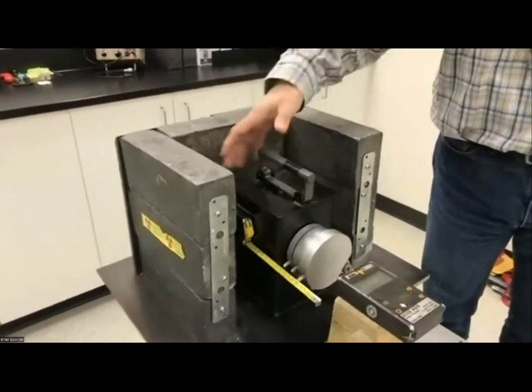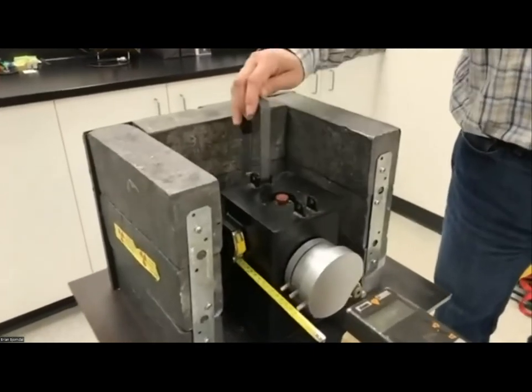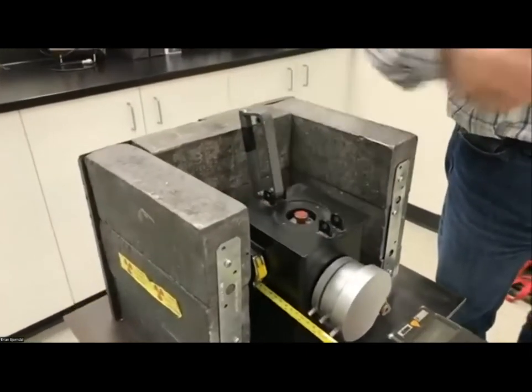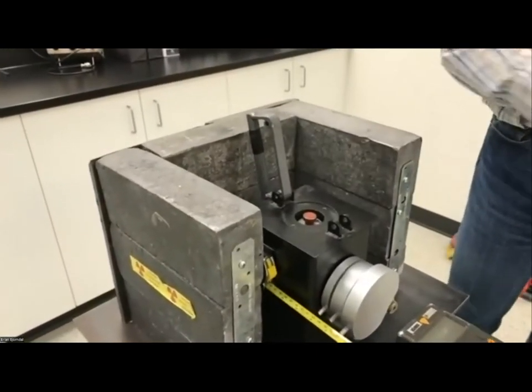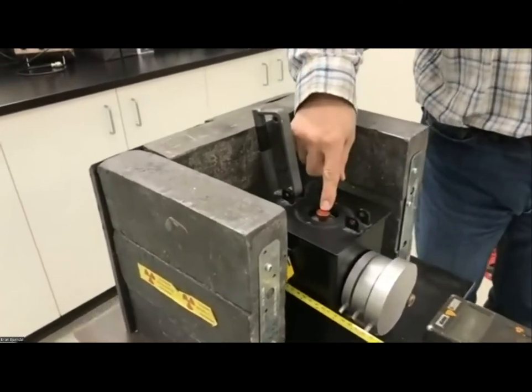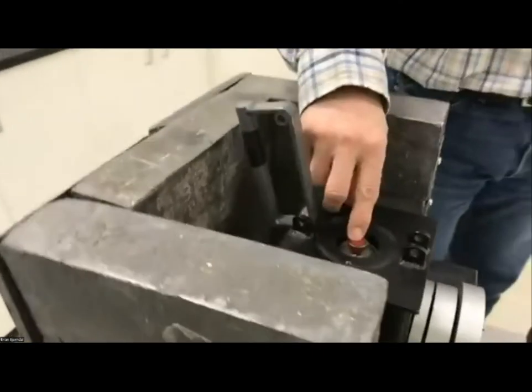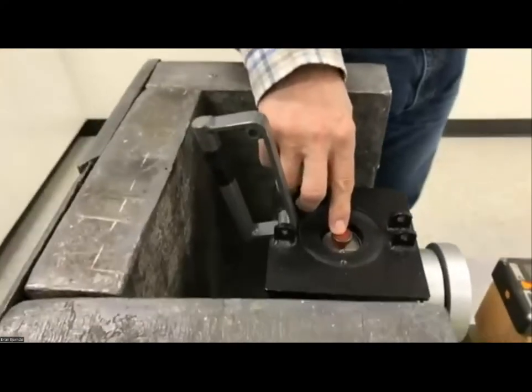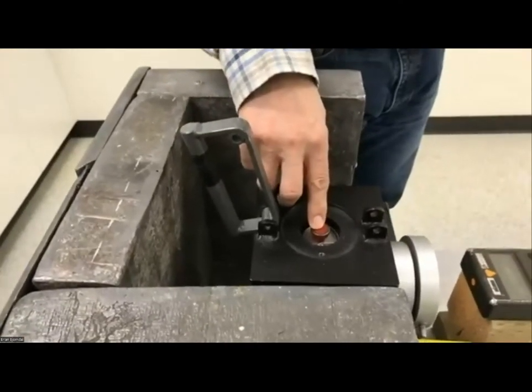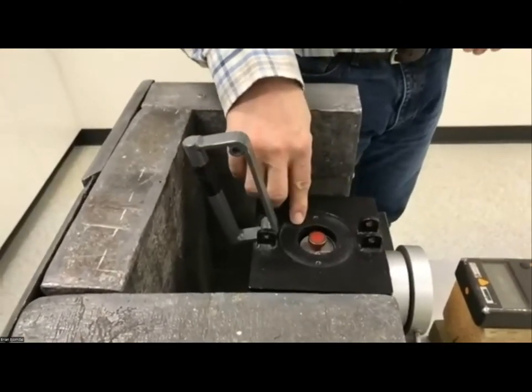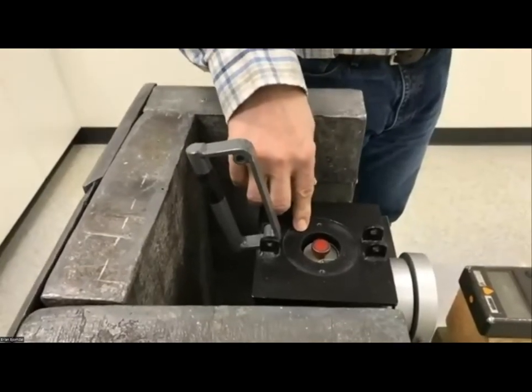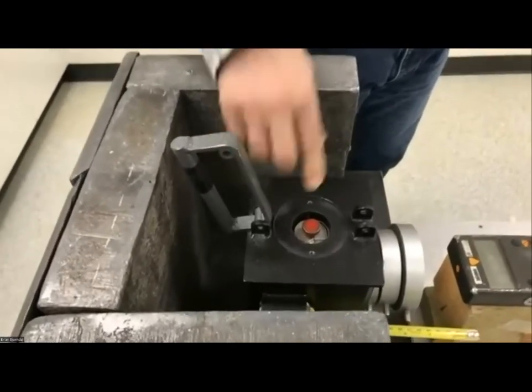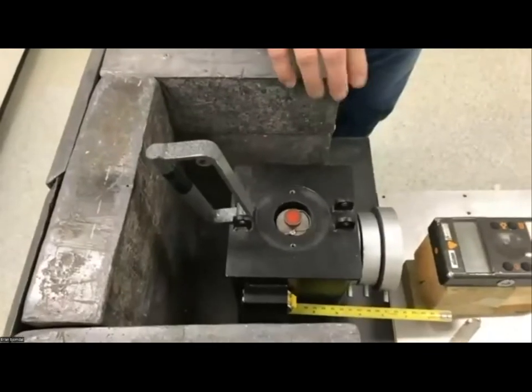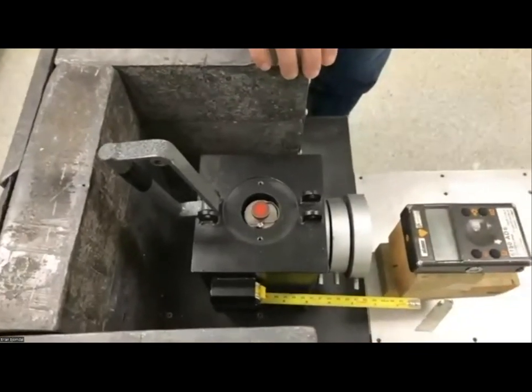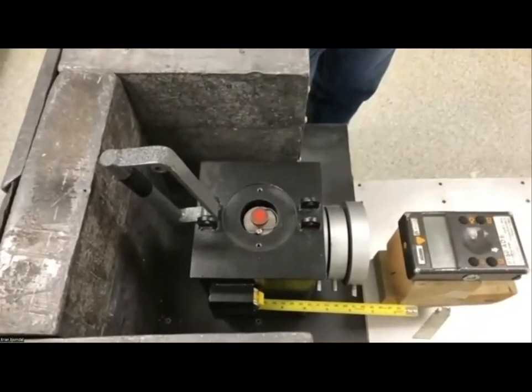It has its own housing and shielding, but inside that device, which is usually sealed off, we pulled it off for time saving, there is a plunger. And inside that plunger is the cesium-137 source. This particular source was 6 gigabecquerels at the time of purchase, which was around 2003, I think, Tabby. So it's getting near about 50% of its activity. Right now it's around 4 gigabecquerels.